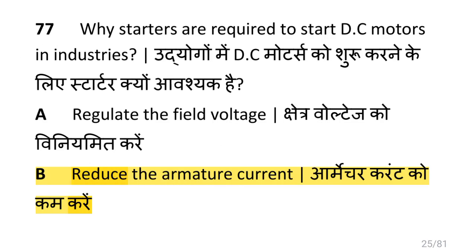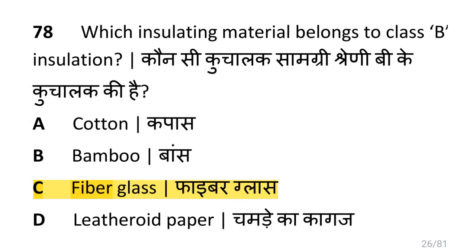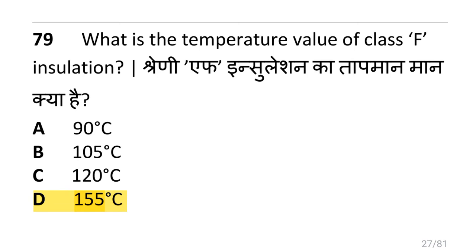Why does the speed control method offer below normal speed in DC shunt motor? That is the armature control method, which offers below normal speed in DC shunt motor. Why are starters required to start DC motors in industries? That is to reduce the armature current. Which insulating material belongs to class B insulation? That is fiberglass. What is the temperature value of class F insulation? That is 155 degrees Celsius.